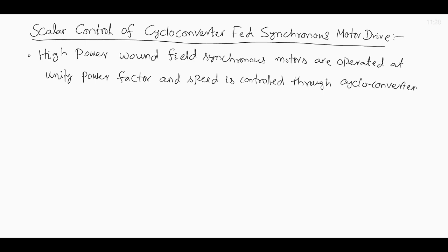Basically, in a synchronous motor the power factor can be any desired value, and the power factor depends upon the excitation or the field current. Particularly in high power synchronous motors, unity power factor is most important because of the high power rating. Reactive power will be substantial even if the power factor is different from unity. So, unity power factor is the most desirable.